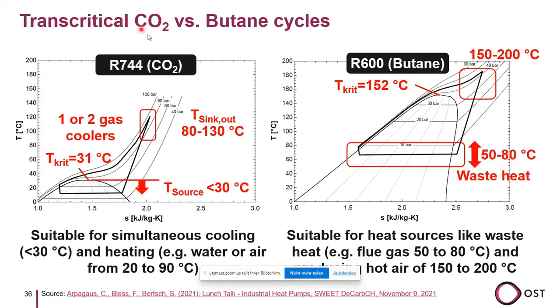The transcritical CO2 cycle is shown here a little bit more in detail. Important is that the heat source needs to be lower than 30 degrees, and the heat sink outlet could be in this range, so around 80 to 130 degrees. And then using maybe two gas coolers in this section. So it's useful for processes which have simultaneous cooling and heating.